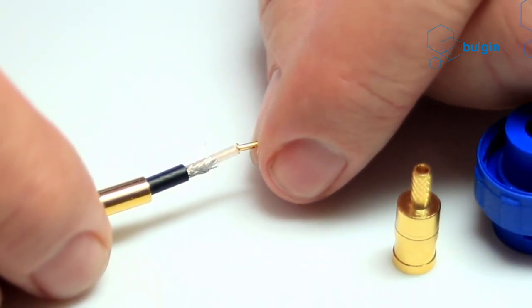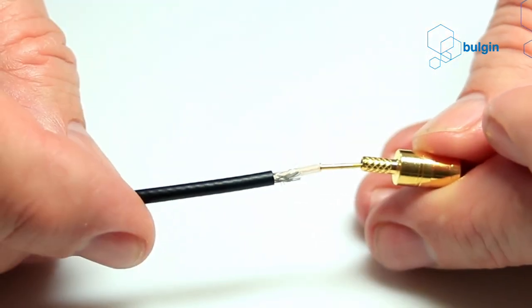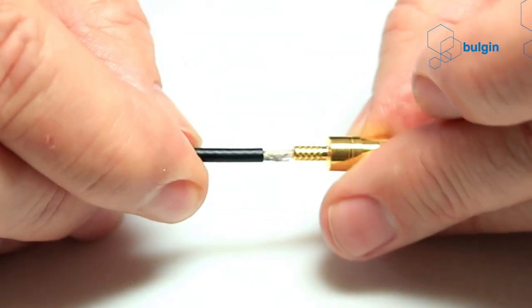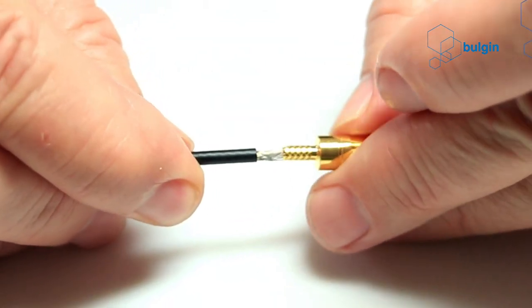However, it is important that installers assemble them carefully. An over-tightened screw could damage the wire, whilst an under-tightened screw risks the wire working itself loose during operation.